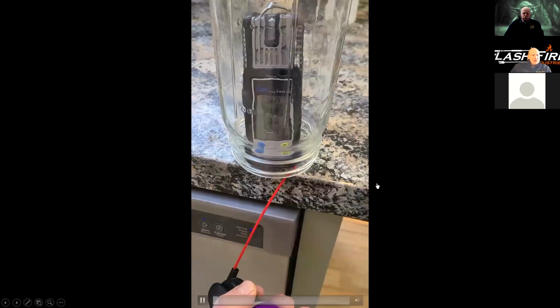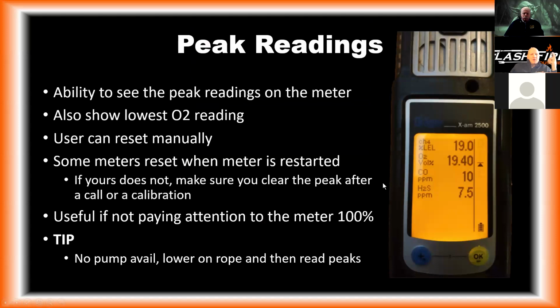range. And so there's no level of acknowledgement. There's no level of letting it sit in fresh air that will reset the meter. I have to turn it off and back on. Side note, don't do that experiment because again, you're putting this stuff right on the sensors. You can spray it in the area of, but we'll talk about that a little bit later as well, because that was something we were seeing a lot with COVID.